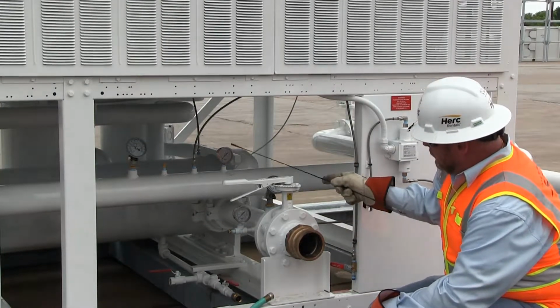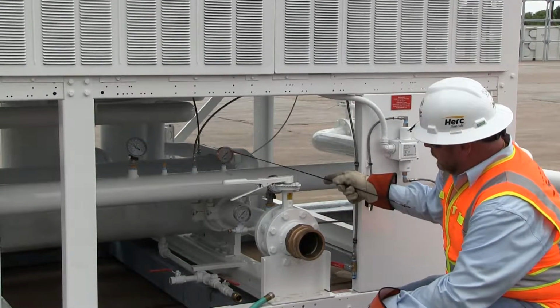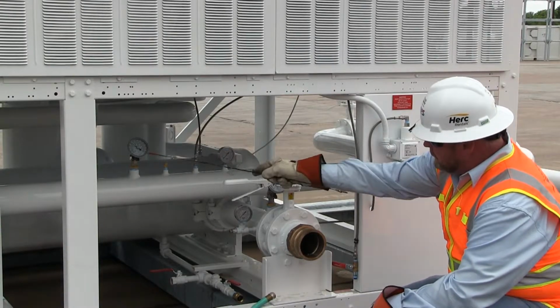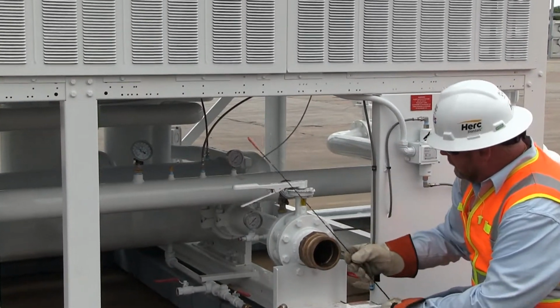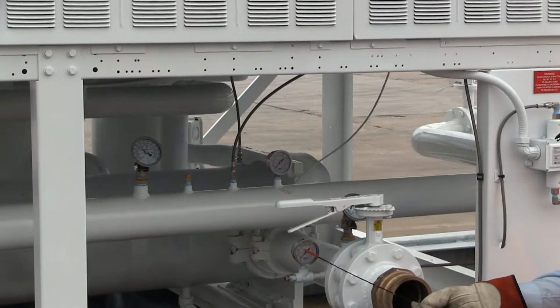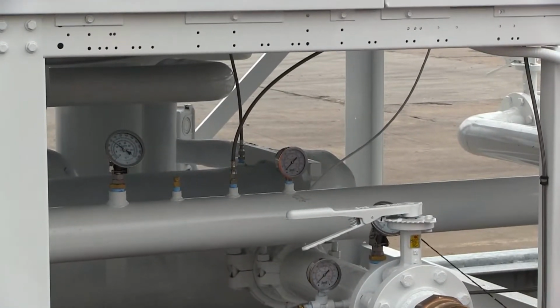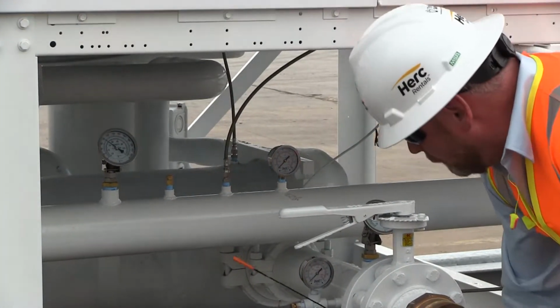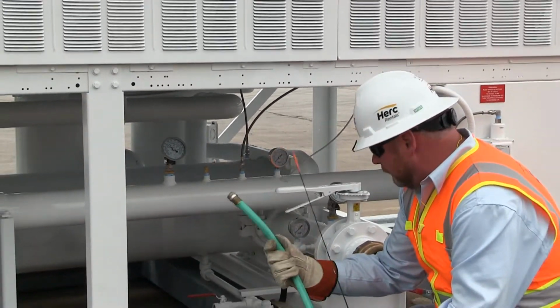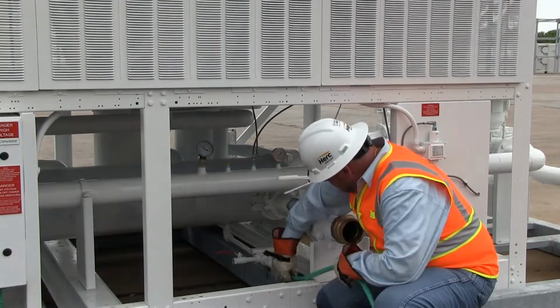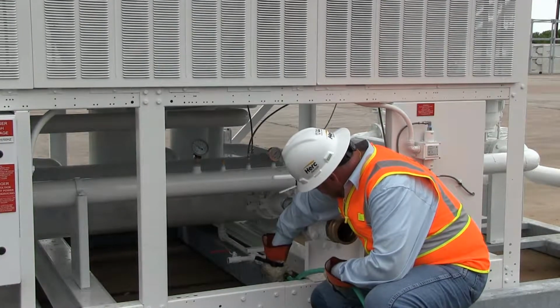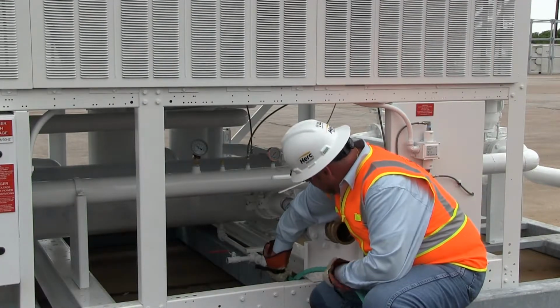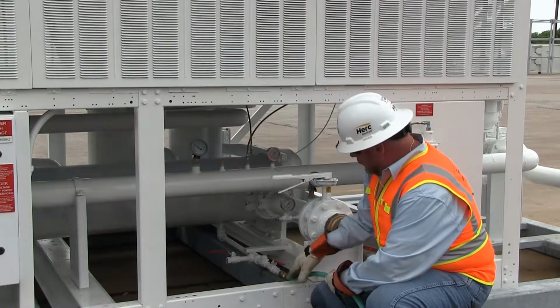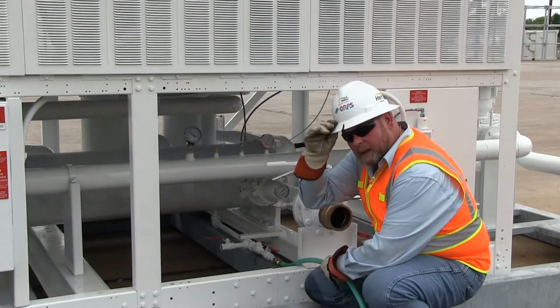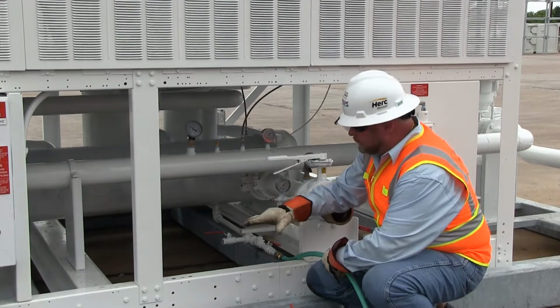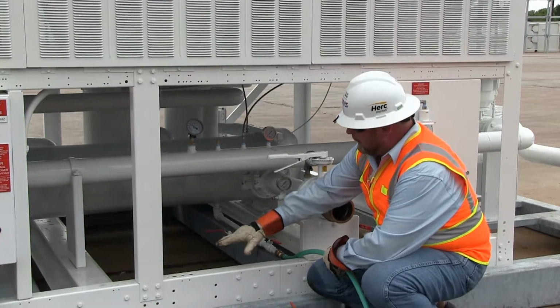The inlet coming off the pump, the inlet to our exchanger, has a compound pressure gauge and a temperature gauge, as well as a Pete's plug, and so does the outlet. The outlet has a compound pressure gauge and temperature gauge here. Then the last items we want to point out is that we're going to hook up our fill line right here to the intake of the valve with the check valve on it, and then this is our drain valve here. So once we connect this 3/4 inch water line up, this will be our fill line to actually start filling the chiller from the bottom to the top.